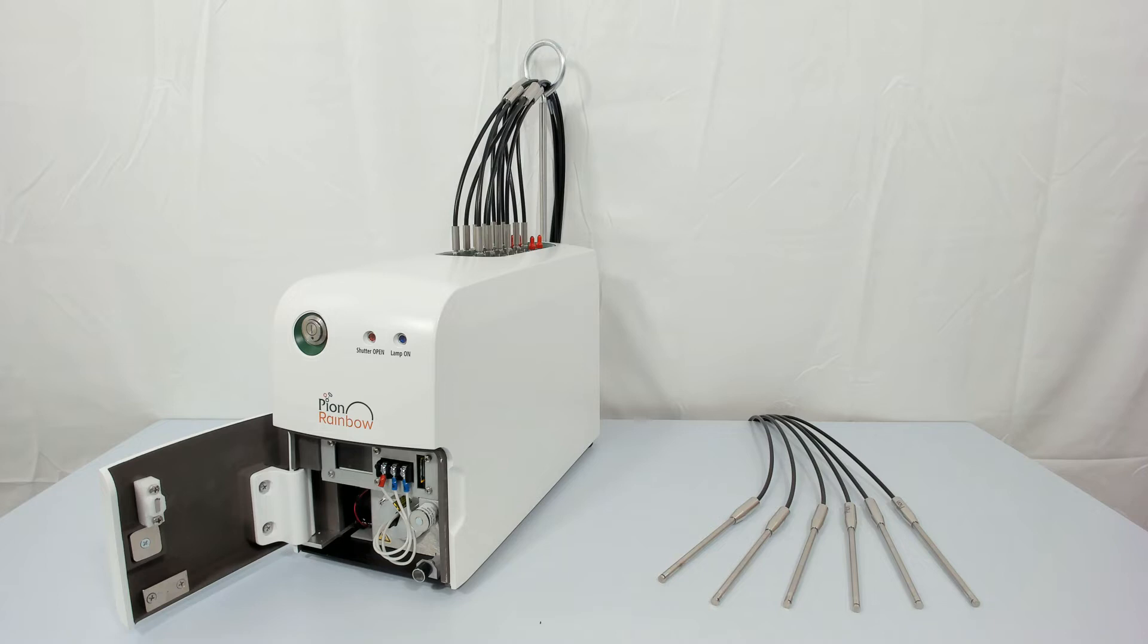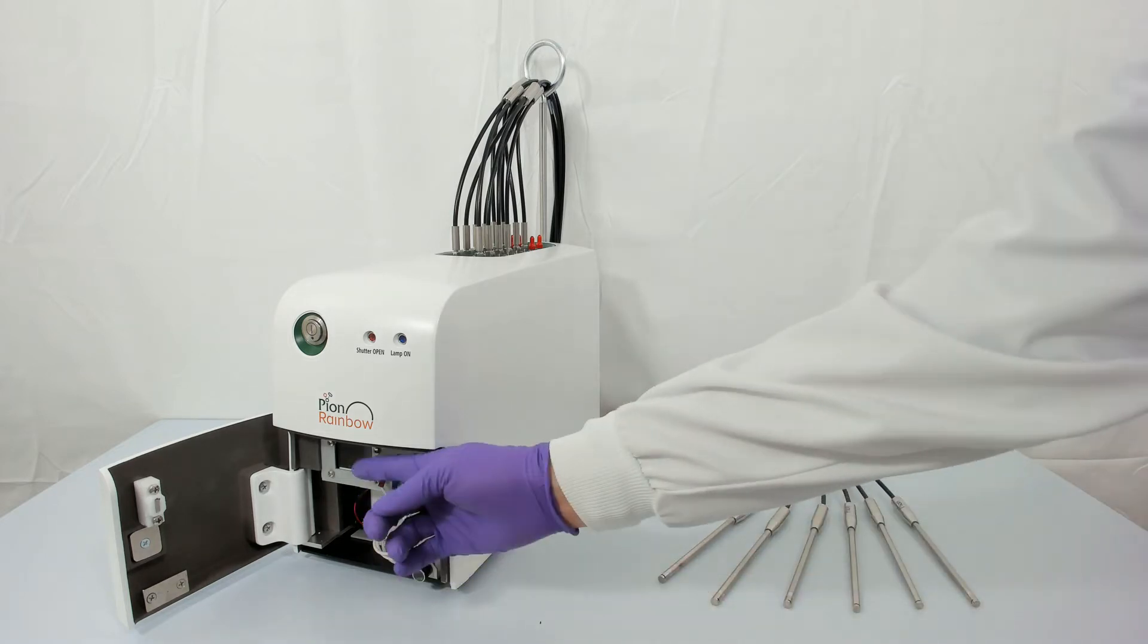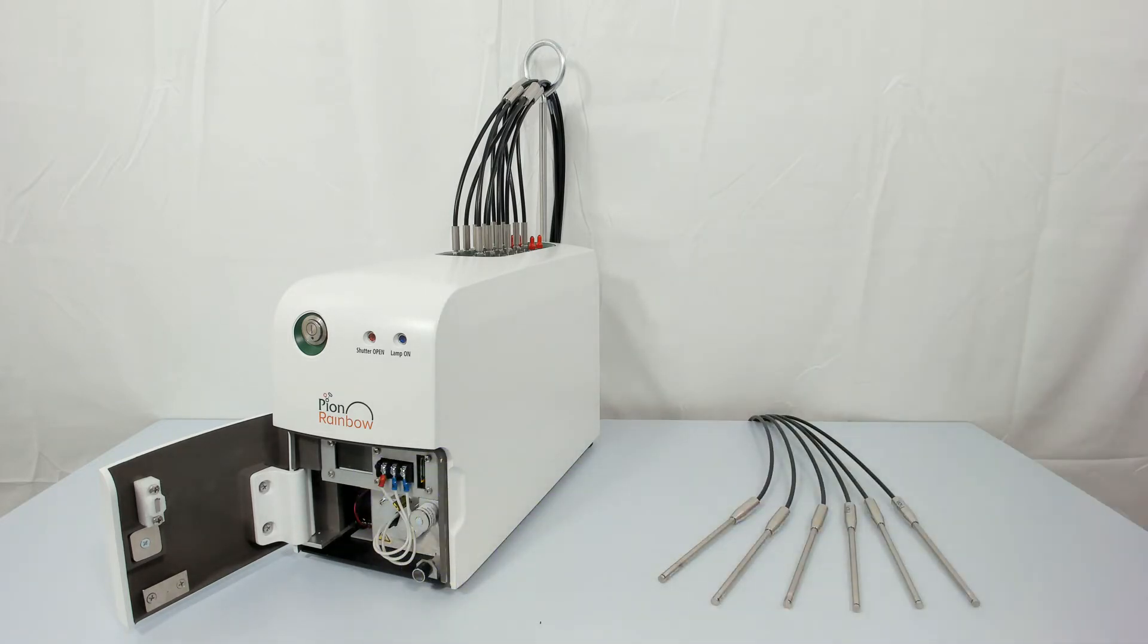The lamp usage time may be read from the screen located here. Integration times obtained for each channel can be expected to increase with the age of the lamp, so in the interests of maintaining optimum performance, the lamp should be replaced every 2000 hours.